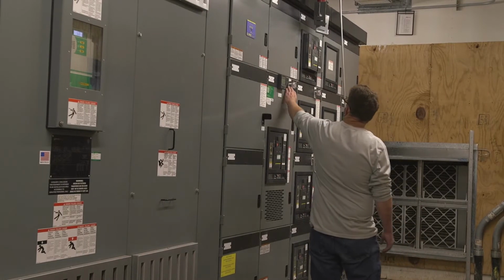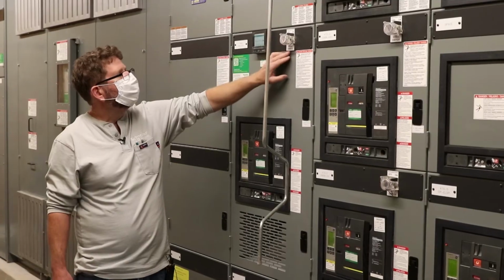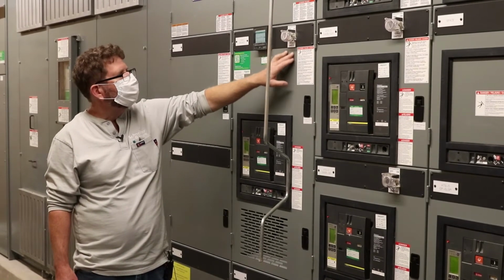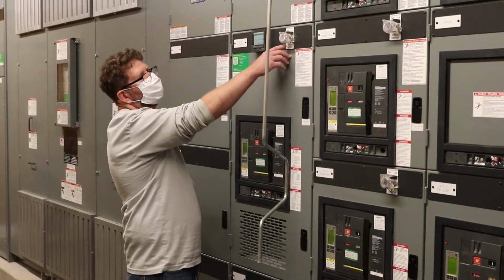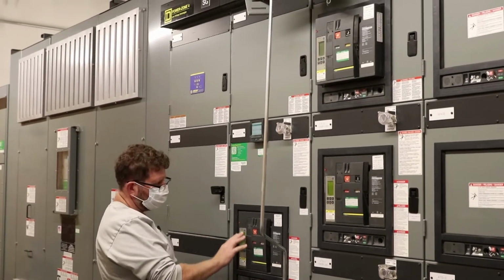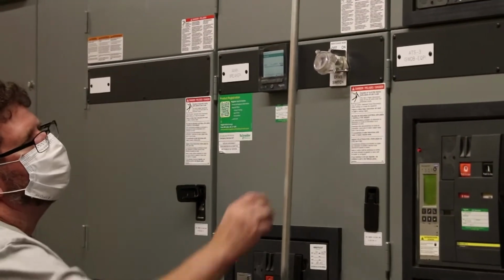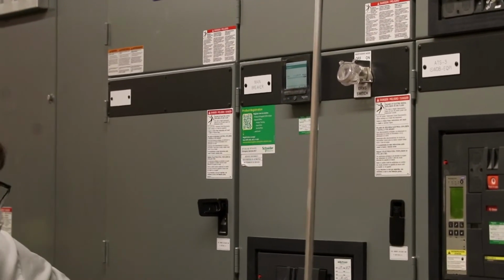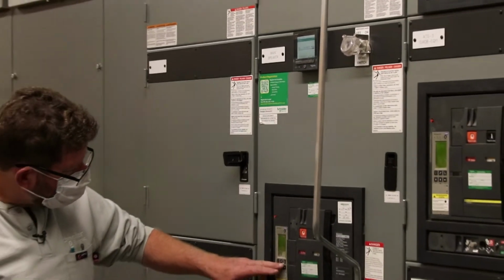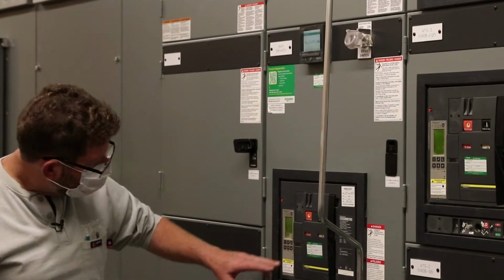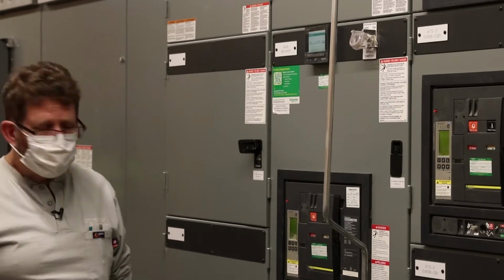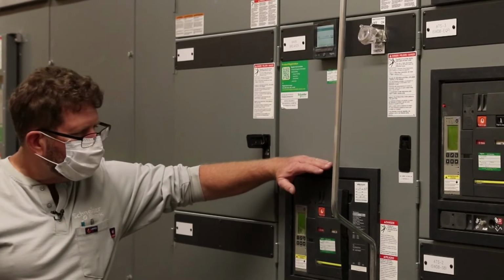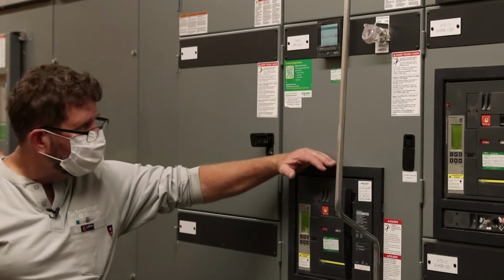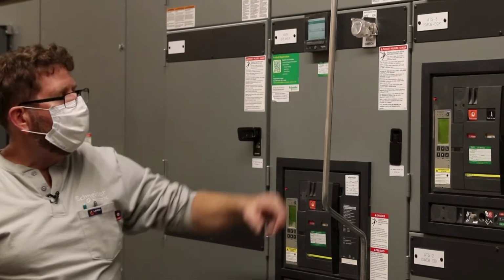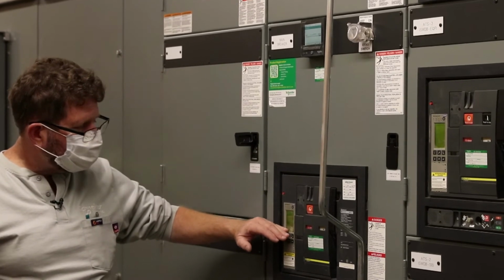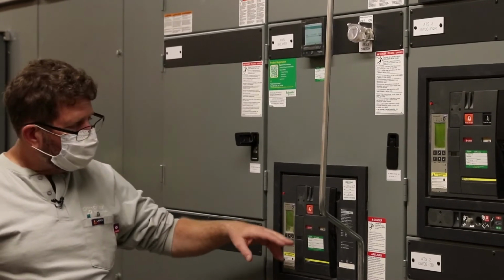Okay, the other thing we have here on the breaker is called an ERMS switch, energy reduction maintenance switch. What that does is, in the off position, it lets all the settings stay per the settings on this trip unit. In the on position, it's going to set the instantaneous down to minimum. Right now, your instantaneous value is set at 48,000 amps. So if this breaker sees 48,000 amps, it's going to trip off with no intentional time delay. If you take this ERMS switch to on, that's going to make your instantaneous setting go down to minimum, which is 2 times, so that'd be 6,400 amps.